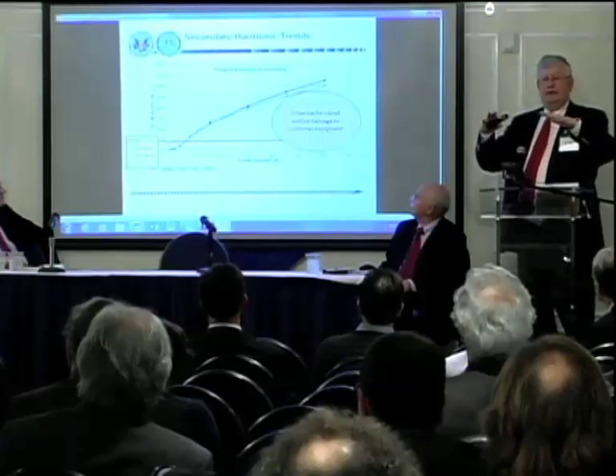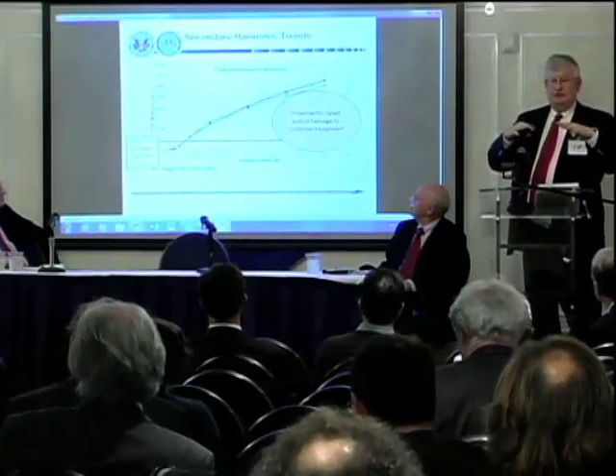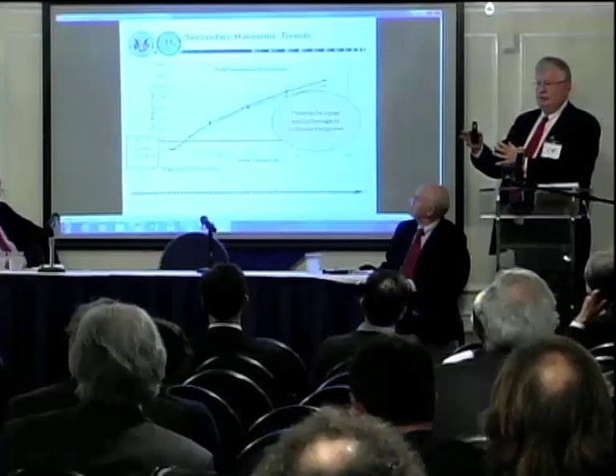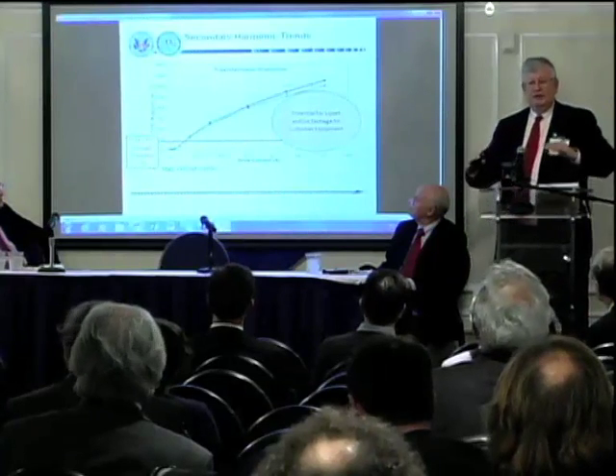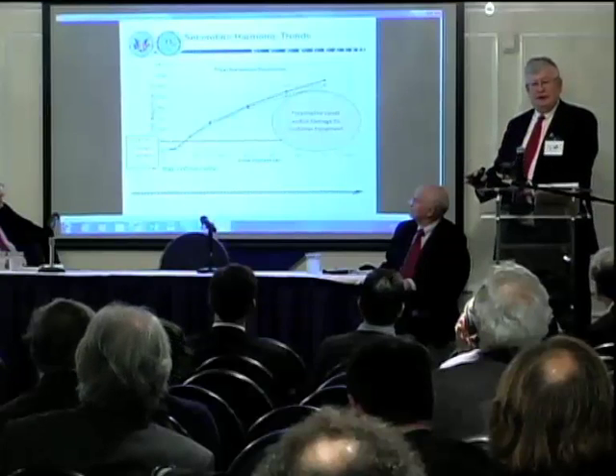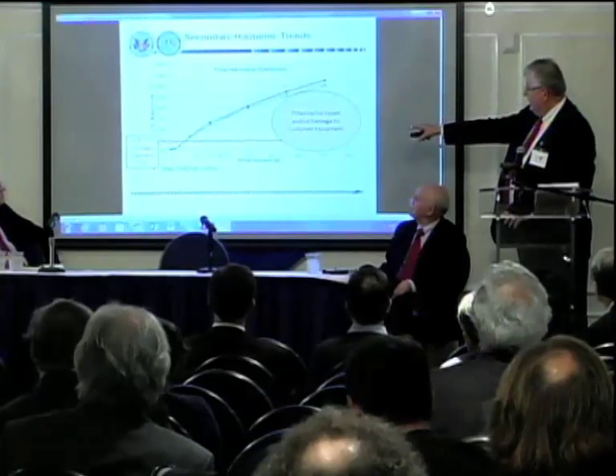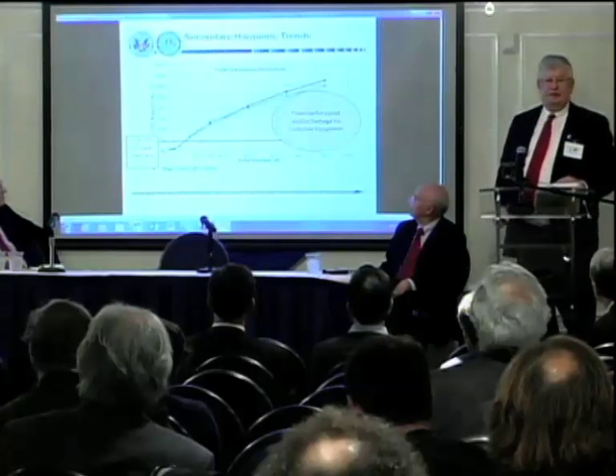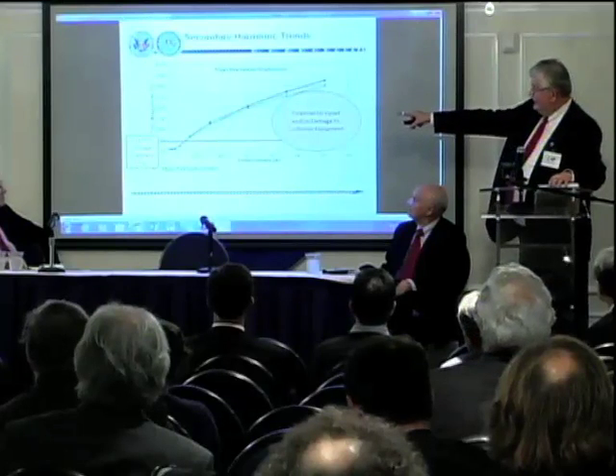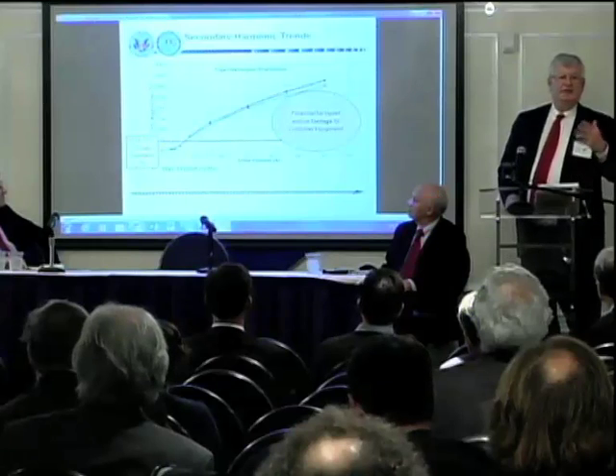Here's a big item. And the utilities have not had the data, perhaps, to focus on this issue until now. Idaho National Labs tested for harmonic issues at the distribution level. The utilities have been focusing on the high voltage level. At the distribution level, you get 33% harmonics at about 100 to 120 amps of current in the neutral. Well, the IEEE standard is 5%, 7.5% for a short period of time.